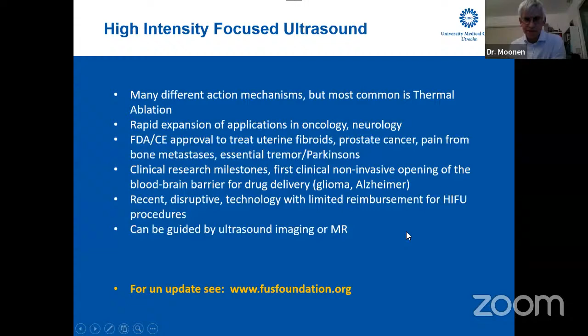Now, if you look here at the hardware, then this is a standard 1.5 Tesla MR system. Inside the bed, that's where the modification is. There is an ultrasound transducer that is embedded in the table top, and you can see this enlarged at the bottom. This transducer is almost as big as a hand, and it's not a single transmitter, but in this case 256 transmitters. They are all firing, and all these beams are coming together in the focal point. It's very much similar to the principles of an optical lens, where you bring them together in the focal point.